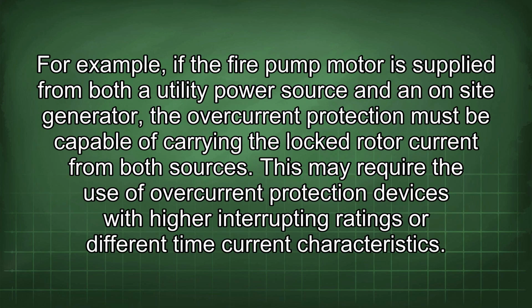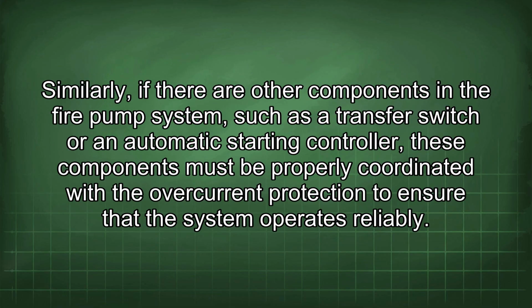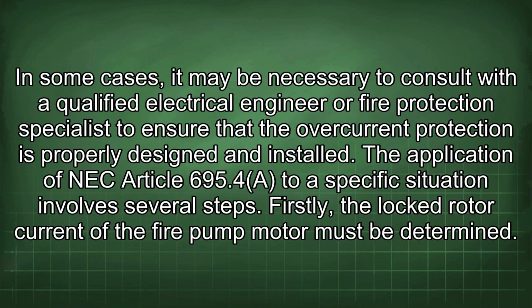For example, if the fire pump motor is supplied from both a utility power source and an on-site generator, the overcurrent protection must be capable of carrying the locked rotor current from both sources. This may require the use of overcurrent protection devices with higher interrupting ratings or different time current characteristics. Similarly, if there are other components in the fire pump system, such as a transfer switch or an automatic starting controller, these components must be properly coordinated with the overcurrent protection to ensure that the system operates reliably. In some cases, it may be necessary to consult with a qualified electrical engineer or fire protection specialist to ensure that the overcurrent protection is properly designed and installed.